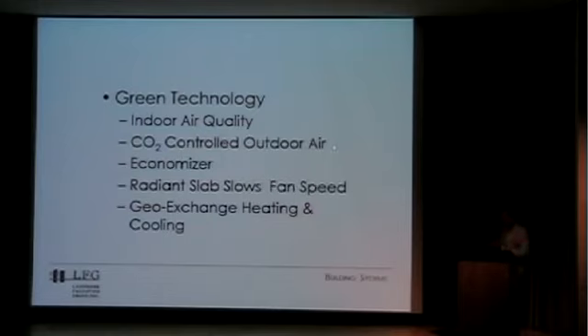All of the occupancy, the outdoor air and ventilation load is controlled based on CO2 sensors. So the building monitors the level of CO2 produced by the number of people inside the space. And as the CO2 level rises, it says, I need more outside air because I need more oxygen. These people are falling asleep. So it starts pumping in more outside air, and it increases how much air is exchanging through the building. And then as people leave, the CO2 levels go back down, and the building can slowly close the outside air intakes, thereby only using how much energy it needs for that particular moment.